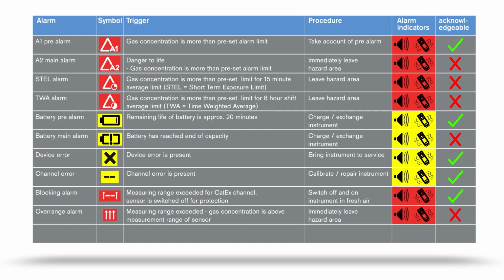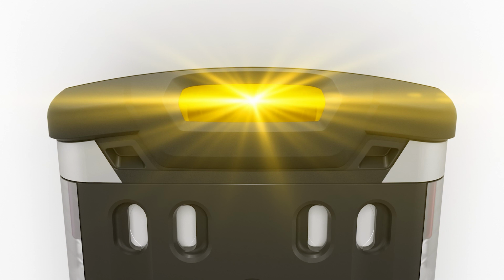If the measured value falls into the negative range, a so-called under-range alarm is triggered. This situation can occur, for example, if a fresh air calibration has been carried out in a range within which concentrations were already present. Please carry out a fresh air calibration in an area where fresh air prevails. In case of a special state, the audible operating signal is deactivated. Special states are indicated by a yellow visual signal on the top LED. No alarm is triggered.